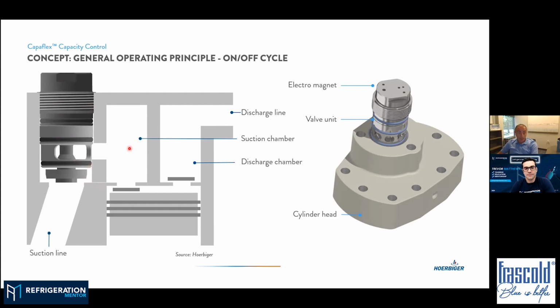And this is the configuration of the compressor. So this is the suction channel. This is the suction side. We have the discharge side on the right. We can recognize the position of the reeds, so the suction reed and the discharge reed. And then we have the discharge line. So in this condition, the compressor would be working at full load.